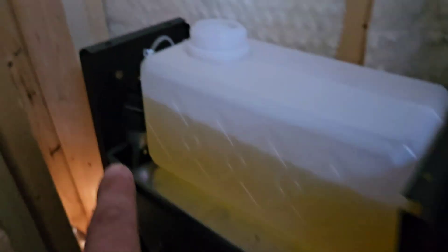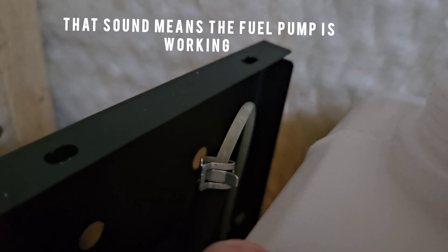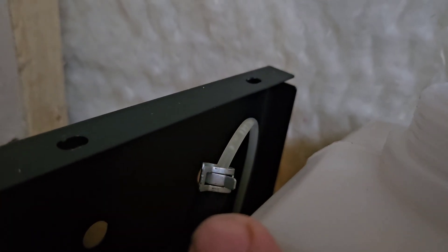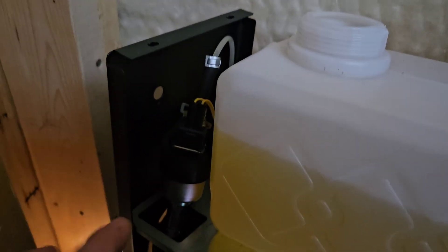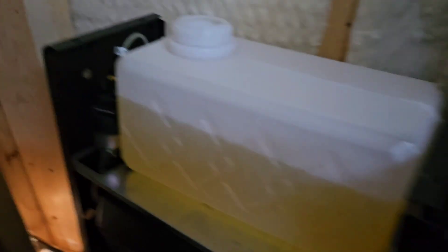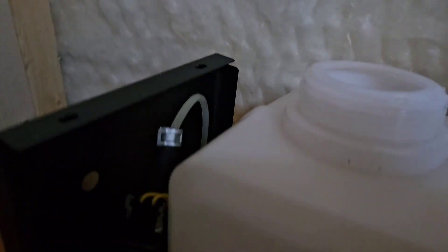things start, you'll know because they blow a ton of hot air. So we're going to let this go for a little bit and see, and hopefully it starts working. You hear that little rumbling, like a little monster? That's a good sign. That's a good sign—it's about to ignite. And even when this is working properly, you'll still hear that. It takes 30 seconds to a minute.